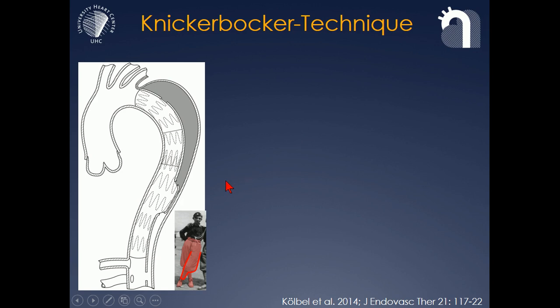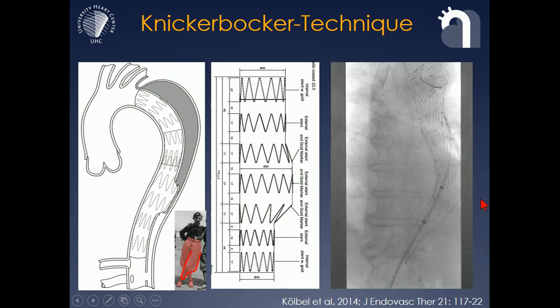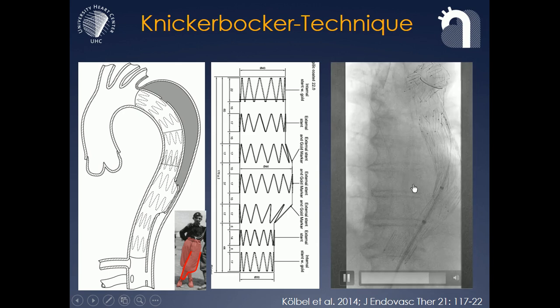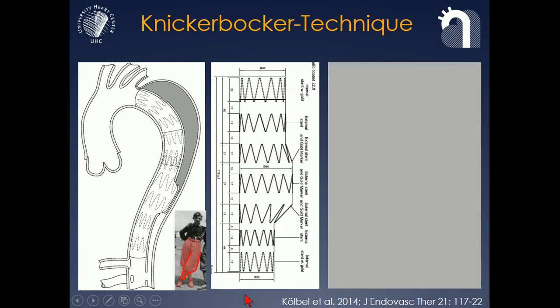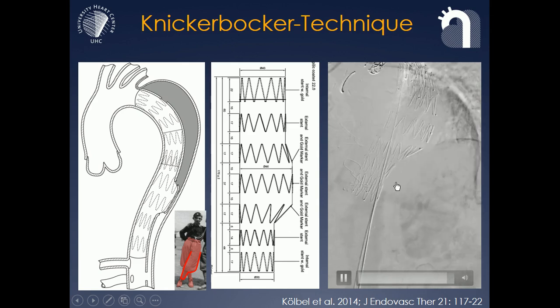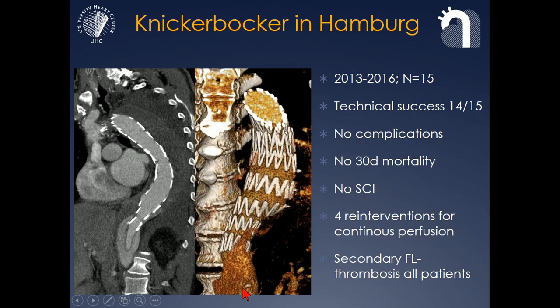Another technique to seal off the false lumen is a little bit similar to what Eric Rosselli just showed us, with balloon dilating stent grafts in the true lumen. We have designed a special stent graft that has a mid-bulge section that allows for the maneuver of rupturing the dissection membrane with a large compliant balloon, so that the stent graft gets this Knickerbocker shape, directing flow to the true lumen while the large section obstructs the false lumen and prevents false lumen backflow. This technique has been successful in most cases; one technical failure was malrotation of the device.